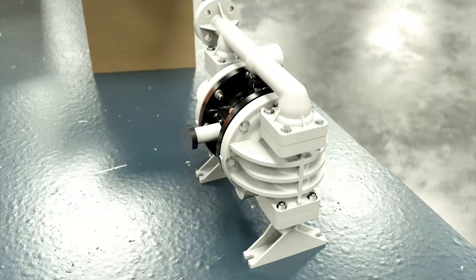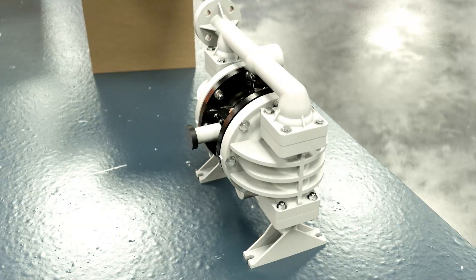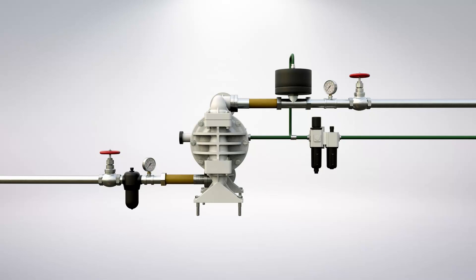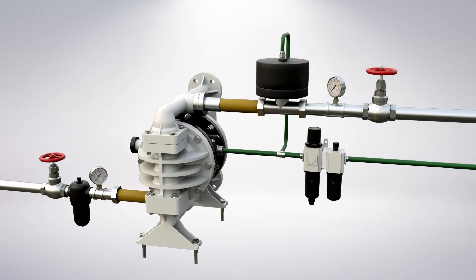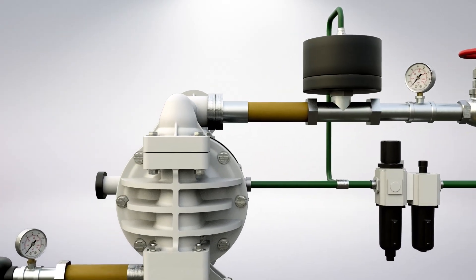Next, install the muffler, which must be installed to reduce sound levels. Install the pump in an accessible location to facilitate future maintenance. When possible, it's best to install the pump using the shortest pipe with the minimum number of pipe fittings.